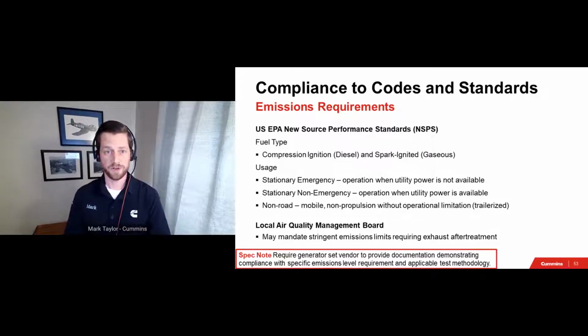As I mentioned before, the generator set manufacturer should be your partner in this process when it comes to precisely understanding their products. Require the manufacturer to provide appropriate documentation demonstrating compliance within the acceptable limits of the US EPA, whether it's stationary, non-stationary, or whether it's emergency or non-emergency. This is also the case with specific emissions level requirements at the local level.